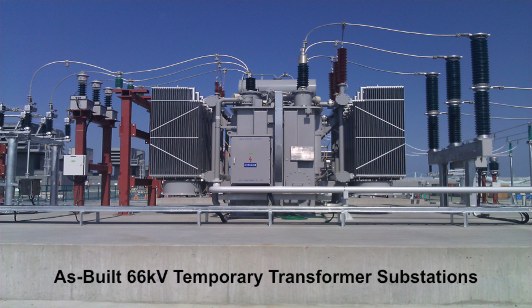These are dead tank circuit breakers. In this instance, we're using 145 kV circuit breakers because the transformers are tappable. Our philosophy as a fast-track company is we buy assets that are very, very flexible. When we're looking at distribution class voltages, everything I do is in 40 kV class. I can use it for 10 kV, I can use it for 25 kV, I can use it for 33, 34 kV. Same circuit breaker can be used across. Then the next big chunk we go into is 145 kV. I can use it for 60, 66, 90, 110, 115, 138. It doesn't matter. Its current rating is good, and the voltage class is good.